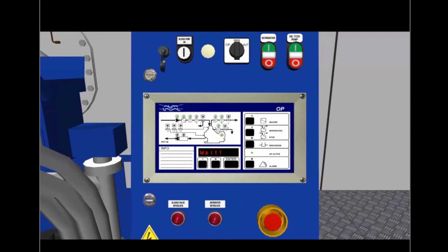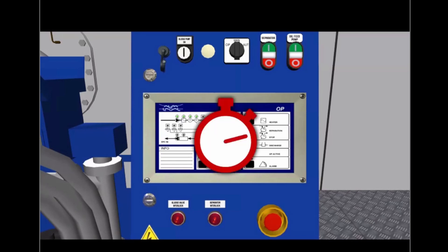Check the oil feed temperature by pressing the plus button until TT1 is shown on the display. Wait until the oil feed temperature is correct. This depends on the type of oil being processed. Heavy fuel oil mode: 98 degrees C. Lube oil mode: 95 degrees C for trunk piston engines or 90 degrees C for crosshead engines. Diesel oil mode: 40 degrees C.